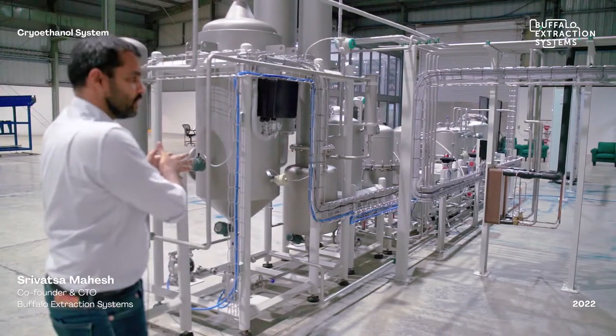As per GMP requirements, we provide all documentation per 21 CFR Part 11 and 211, or per EU GMP requirements of Annexure 11 or Annexure 15. In addition, the system is completely CE certified and ATEX certified, which is why all components in areas where ethanol is present are flame-proof, and all connections involving utilities or non-flame-proof parts are kept in the utility area.